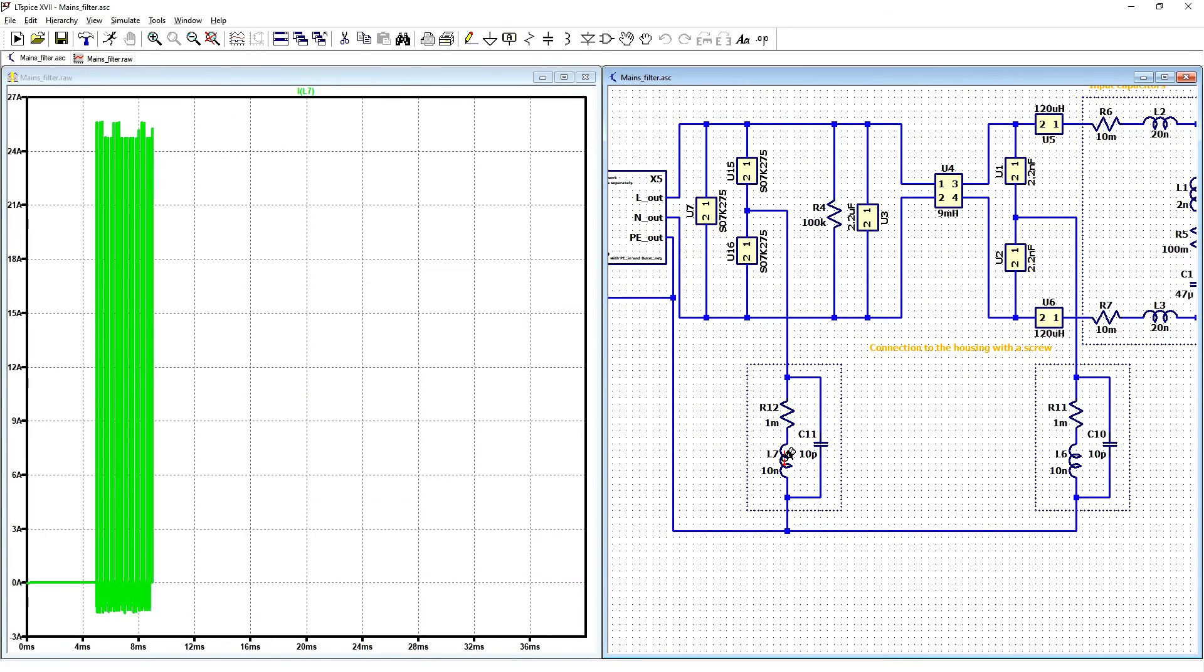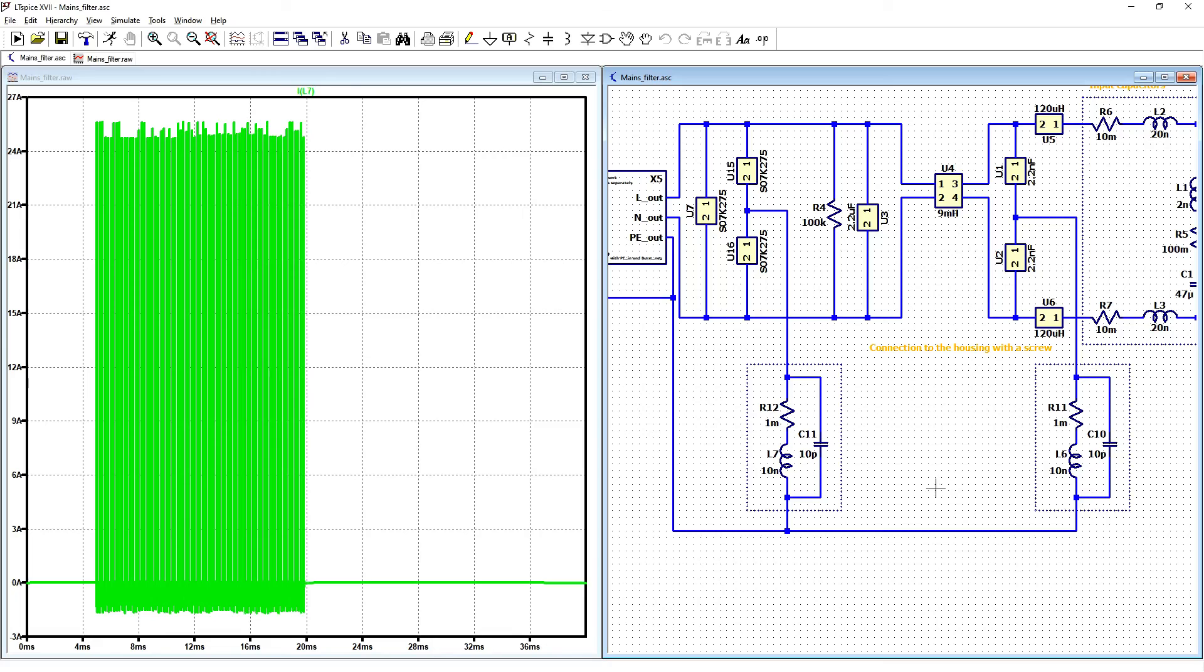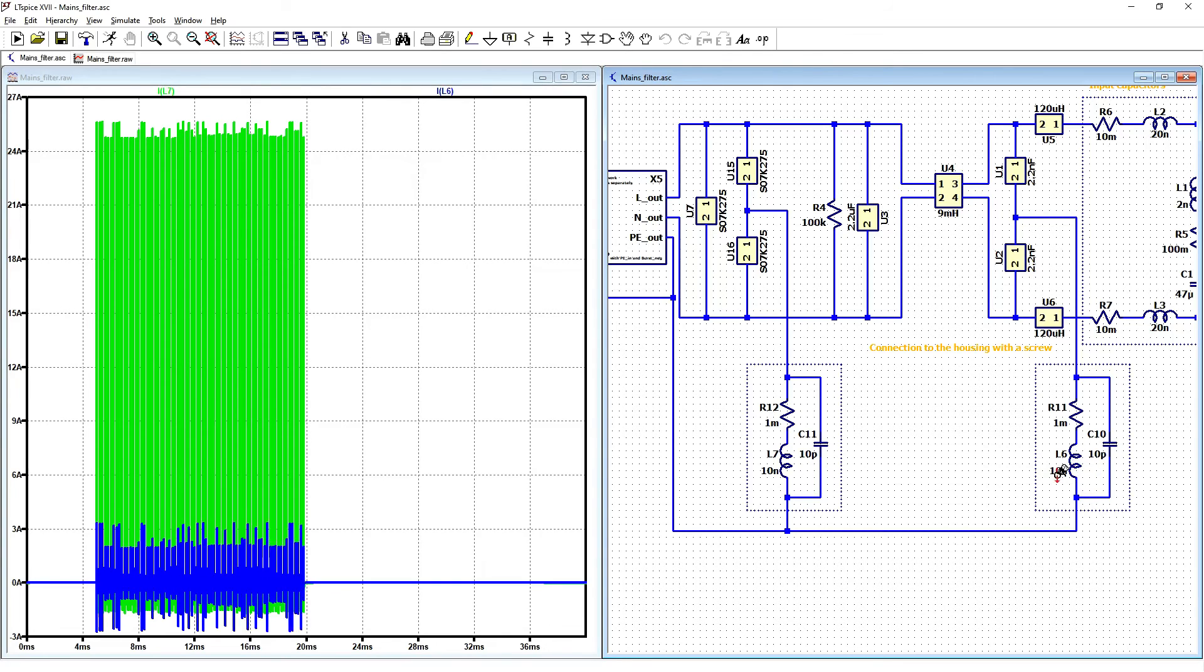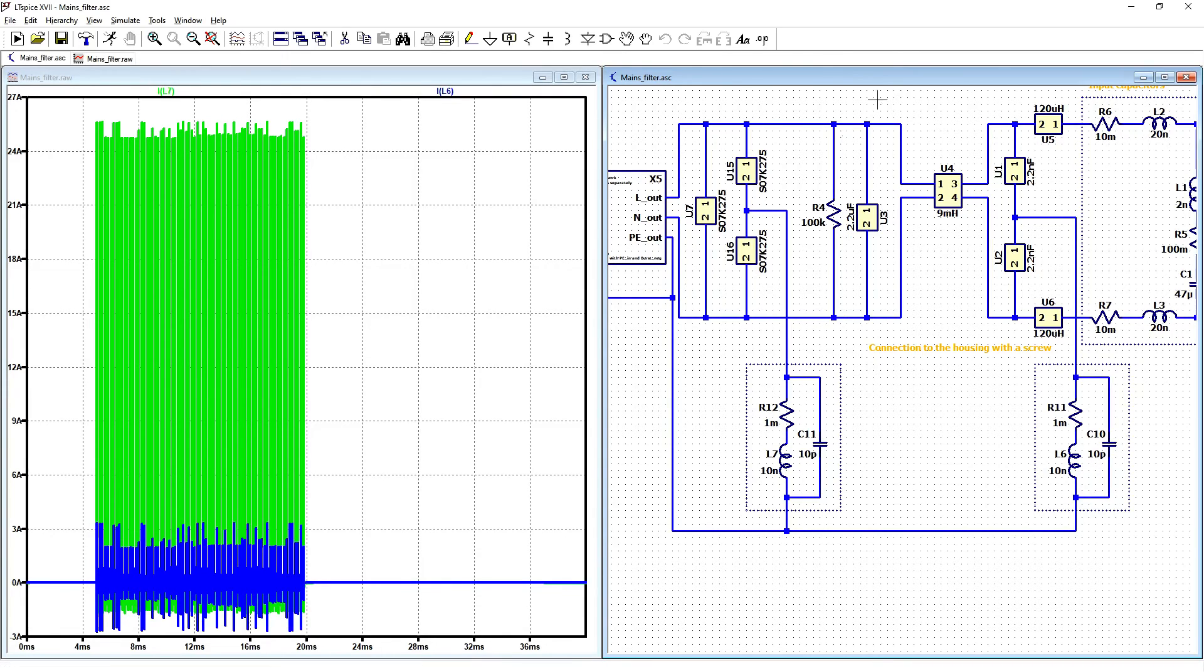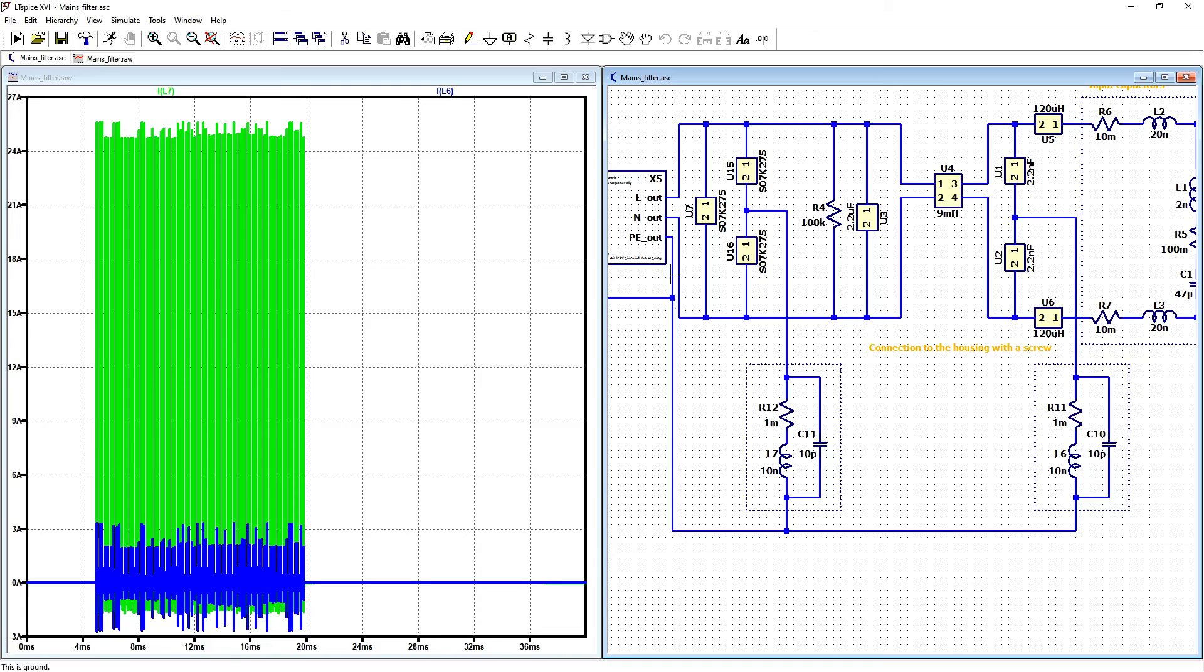We can also compare how much current is going through the screws, so inductance here, almost above 24 Amperes and here above 3 Amperes. CX capacitor and CY capacitor are doing here a lot. First point of connection to protective earth and second point of connection to protective earth is doing a lot of filtering.